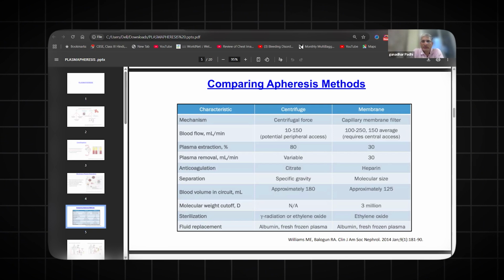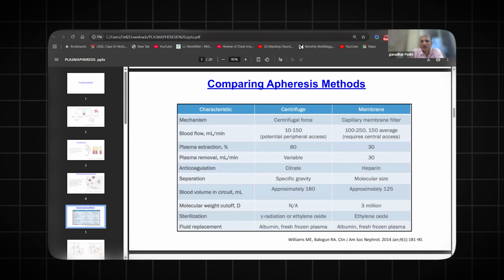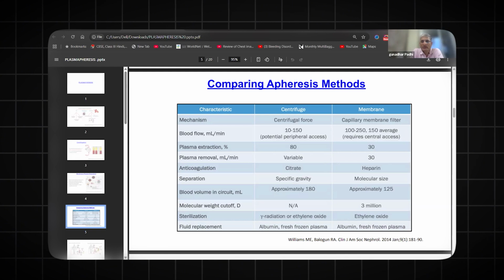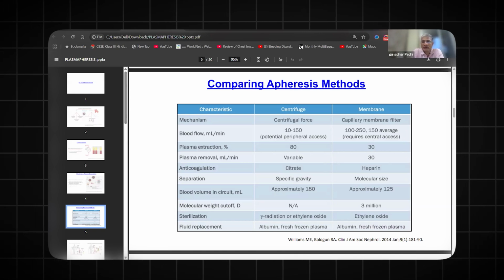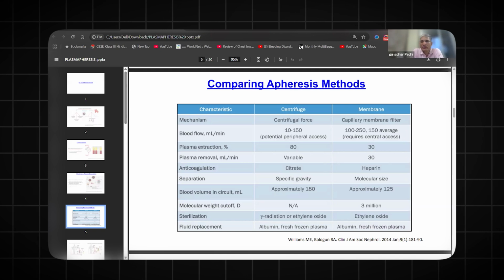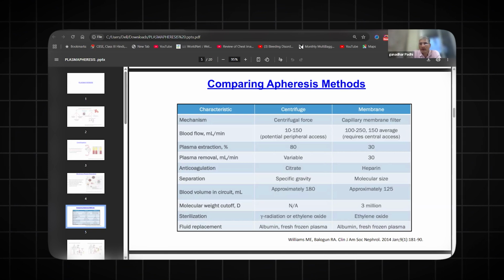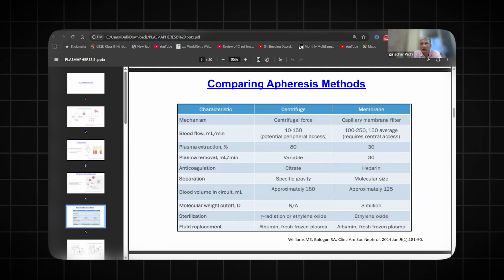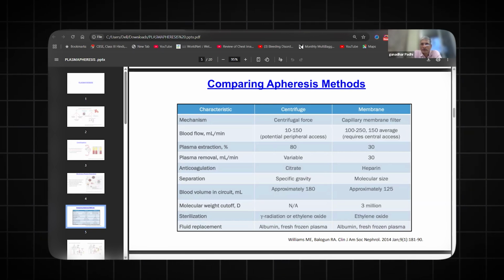So most of the time, within the first 15 minutes, if the patient complains of numbness, tingling, perioral numbness, or hypocalcemia signs like tetany or carpopedal spasm, then it is more likely due to hypocalcemia. So hypocalcemia is one of the very well-known complications of the centrifugal plasmapheresis technique. Whereas, as you know, membrane plasmapheresis employs heparin or sometimes citrate. If it is a CRRT-based plasmapheresis, most of the time they employ heparin, and heparin is an agent which also causes anticoagulation in the patient's body. So that is the reason there is a chance of bleeding and a chance of coagulation dysfunction after the plasmapheresis is over. So you have to always check the patient's different coagulation parameters.